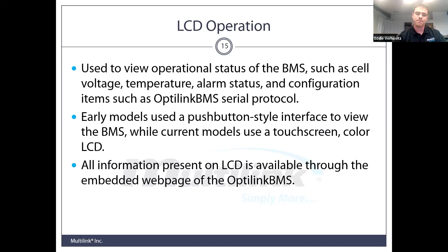With our LCD operation, anything that's available on the LCD of the Pantheon cell battery itself can also be viewed through the embedded web page of the Optilink BMS if it is in use. So for troubleshooting steps, we'll just touch on a few of them. We'll have a full list of troubleshooting items and any mitigation steps that you might need in our Pantheon cell user manual. But the first source of troubleshooting is to verify operation through the LCD as well as the LEDs. Any active alarms that may be apparent inside of the Pantheon cell battery will be shown in the status menu and will be clearly indicated as a source of any of the issues that may have occurred.